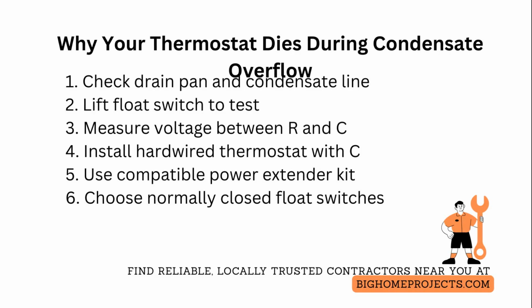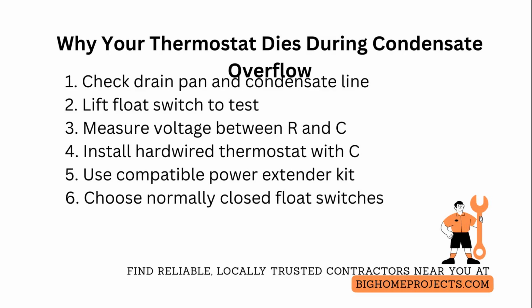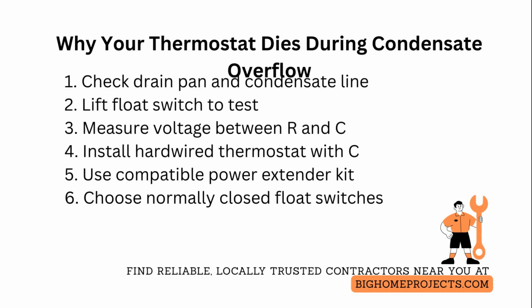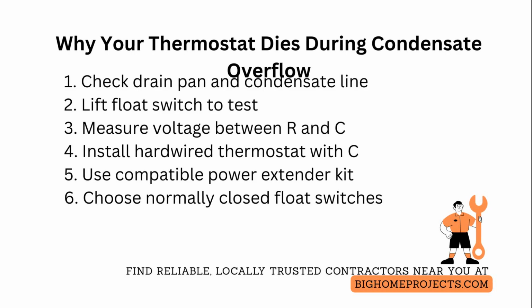A battery-only thermostat will still light from its own batteries, but can appear non-functional because the thermostat needs the R and C circuit behavior to call for cooling or to show system status. First, check the drain pan and condensate line for clogs and confirm whether the float switch is engaged by physically lifting it and seeing if the HVAC restores power. That isolates whether the float is cutting the R wire.